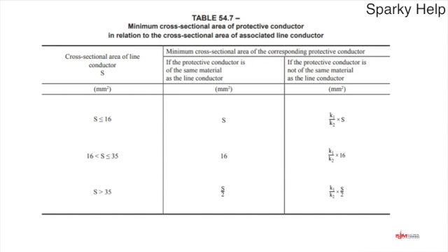If we look at the middle column, which is the one relevant to us in this very easy guide, if you have a 1 mil cable on the left hand side as your line conductor, then the second column says your CPC must be the same size. In fact, you keep the CPC the same size as the line conductor up to 16 mil. If you do this, you do not need to calculate, it will work. Going on down, the next one is greater than 16 and up to 35 mil, so that's 25 mil and 35 mil cables.